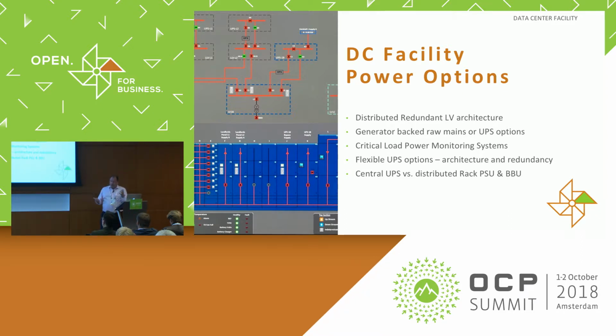One of the things you need to look at with the OCP battery backup units is local regulations - we heard about the German case where you can't put the battery within the space - but also the economics. Is it more economic to provide one UPS to cover the whole installation if most of the infrastructure needs it, or do you go back down to the rack and groups of racks accordingly? So you need real thought about what you're designing for.